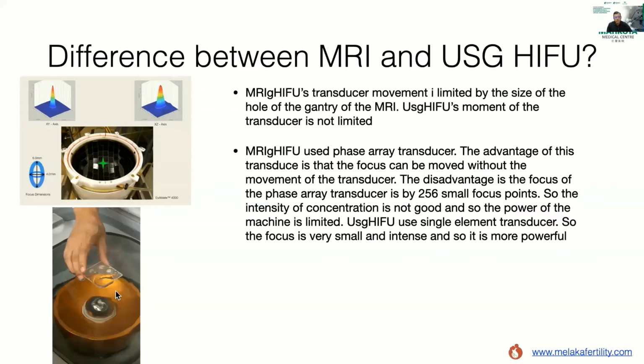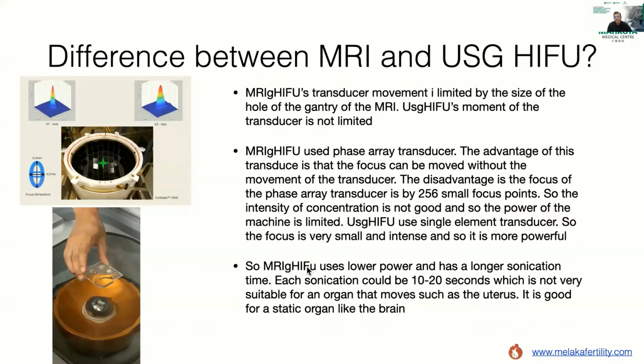As opposed to that, in ultrasound-based HIFU, this is the whole transducer. There's only one, a single element transducer. So the focus is very small and very intense, and so it's much more powerful. What happens in an MRI-based HIFU is that the power is lower, so you have to do sonication for a longer time. Each sonication could be 10 to 20 seconds, which is not very suitable for an organ that moves, such as the uterus. The uterus doesn't sit still; it moves as the patient breathes. So MRI-based HIFU is very good for a static organ like the brain.